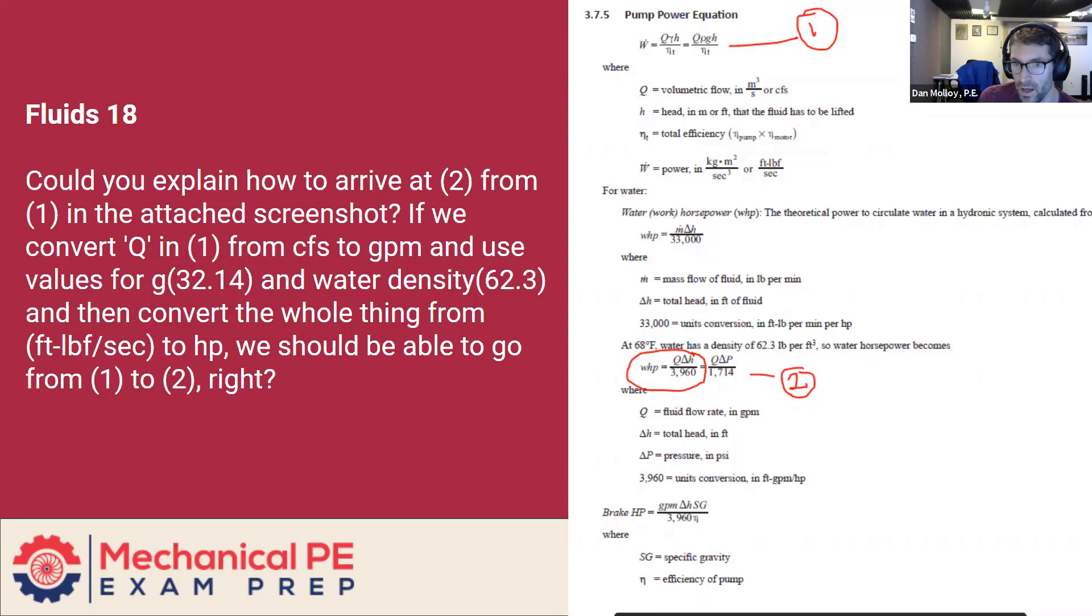If we convert Q, the volume flow rate, from cubic feet per second to GPM, and we use values for G, 32.14, and for the density of water, and then convert the whole thing from foot pounds per second to horsepower, we should be able to go from one to two, right? Yes, we should be. So let's try. I put together a quick example to illustrate those two, and hopefully we can reconcile those two formulas together.